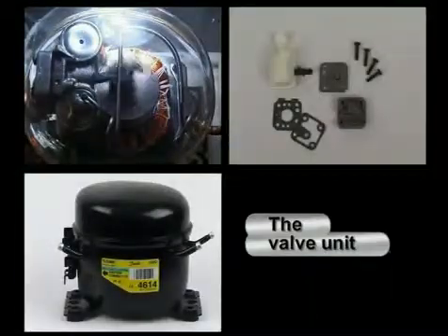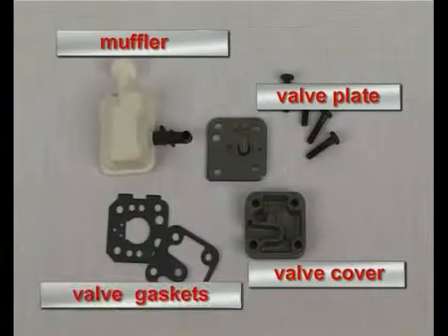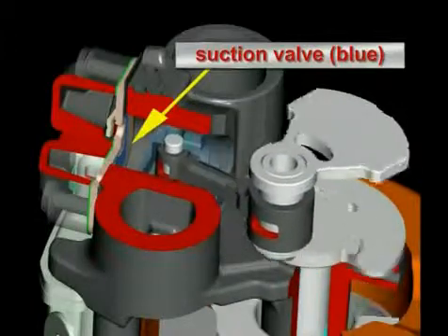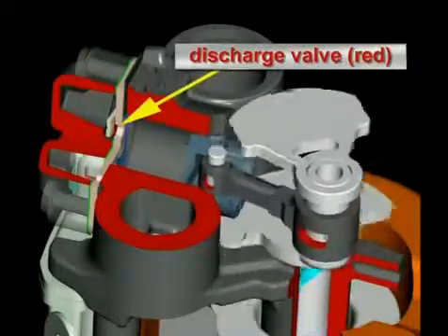The valve unit essentially consists of a valve plate, a valve cover, a muffler, as well as two valve gaskets. The suction and the discharge valve are installed on the valve plate. Both valves are reed valves made out of spring steel, and they open and close the openings of the valve plate during the suction and discharge process respectively.